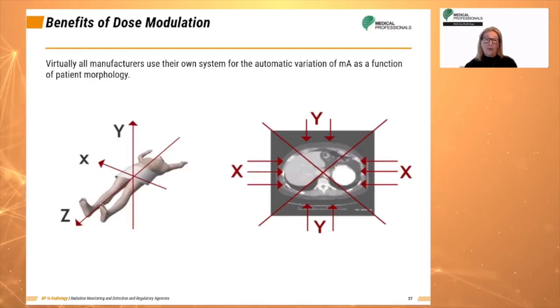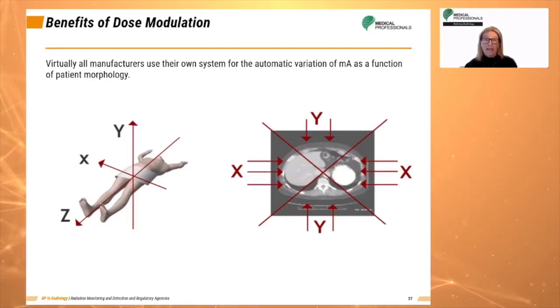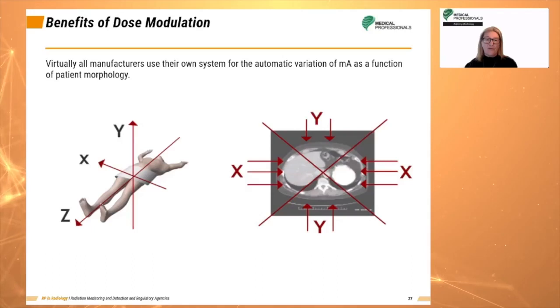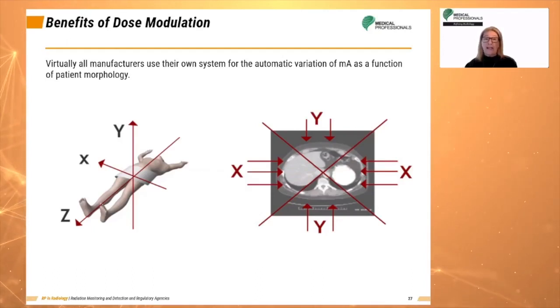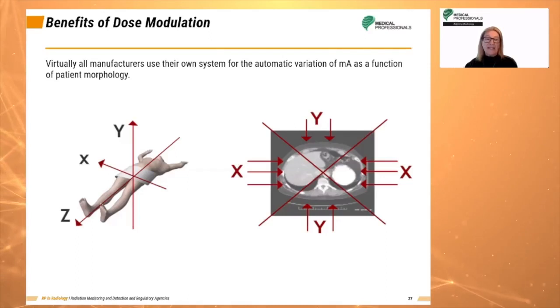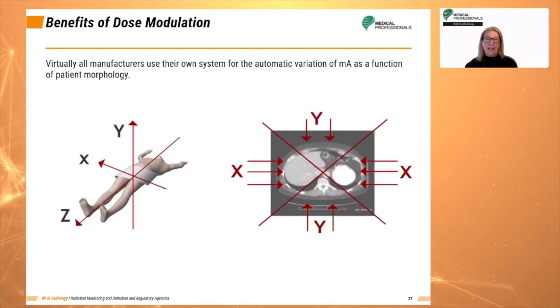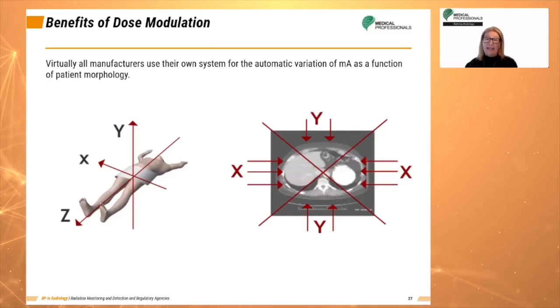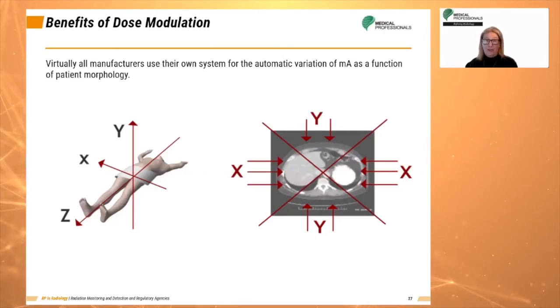Variation is a three-step process, and virtually all manufacturers use their own system for automated variation of MA as a function of patient size. The steps are: first, determine the overall patient size and use the same dose in mA for the entire examination distributed according to morphology; second, the Z-axis delivers a suitable dose within each tube rotation; and third, the X and Y axes modulate dose at each rotation as a function of patient dissymmetry in the axial plane.